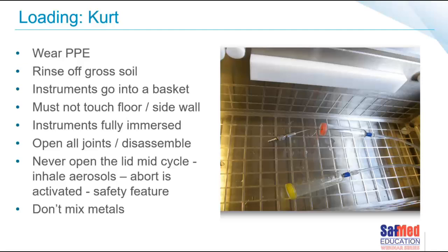So that's very important. Rinsing off gross soils, once again, we spoke about it earlier. All gross soils must be rinsed off the instruments before loading them. A lot of times, as I mentioned earlier, we are under pressure. We pack the instrument straight into the basket, whether it's connected or not, and we assume the ultrasonic cleaner is going to do its job. And of course, it won't be coming out clean at the end of the cycle. Instruments going into the basket. A lot of times I'll find, or if I'm in the CSSD, we find that the basket has been removed to either do the morning check for the filters, clean or dry the bath out, and we put instruments directly into the bath and not into the basket.